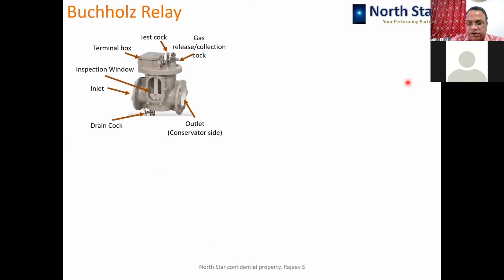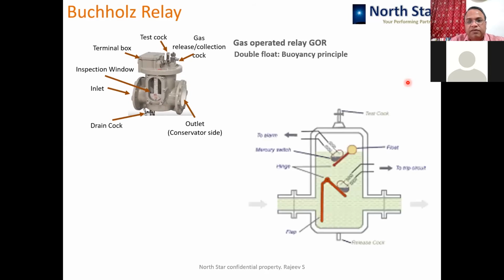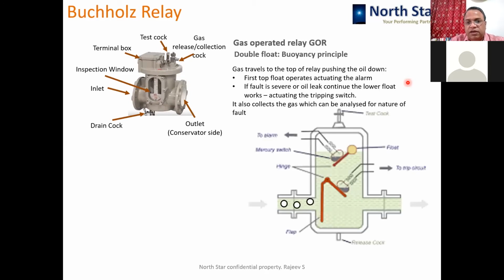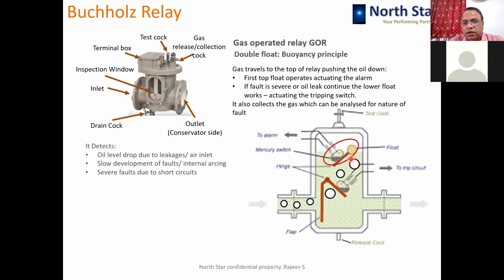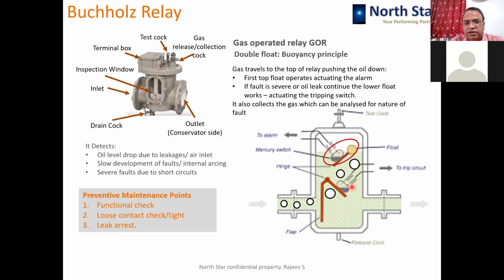The Buchholz relay, you all know, is a gas operated device and works on the buoyancy principle. Here you can see the gas is getting formed and rising above and operating this float. So this float gets operated, you get a signal, and you can use it as an alarm. If further gas gets generated, the lower float operates and you can use it for the trip circuit. So this is a beautiful protection device and can give you a lot of comfort from incipient bigger failures.